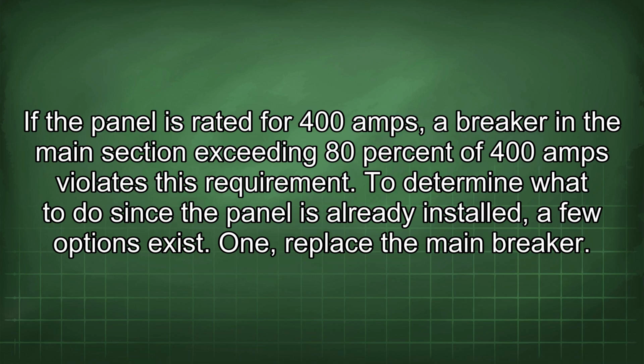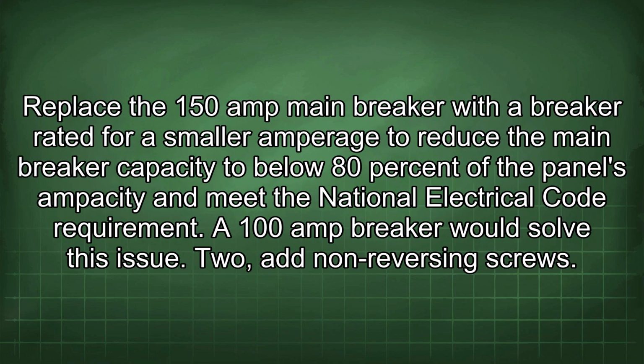1. Replace the main breaker. Replace the 150 amp main breaker with a breaker rated for a smaller amperage to reduce the main breaker capacity to below 80% of the panel's ampacity and meet the National Electrical Code requirement. A 100 amp breaker would solve this issue.